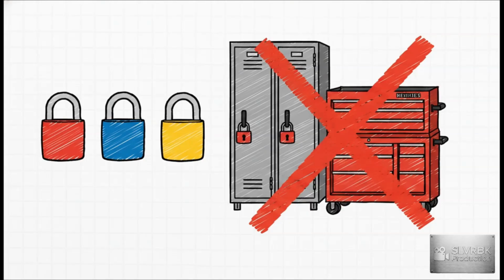Whether you're using a lock or a tag, the real OSHA mandate here is strict standardization. These devices have to be uniquely identified within your specific facility by color, shape, or size. And here's the golden rule, folks. These locks and tags cannot be used for anything else. You cannot take your assigned red LOTO lock and use it to secure your gym locker or your personal toolbox. No way.